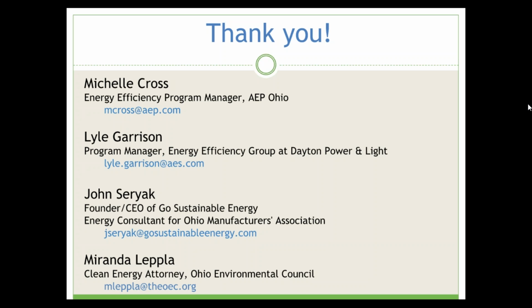Yeah, this is John. I think the answer is yes, it can be, and it's a cost-benefit thing. If you're going to be providing ancillary services or putting electricity onto the grid, it's not necessarily the same dollar per kilowatt hour rate that you get when you're saving versus when you consume. So you have to pencil it out. I think most projects intentionally cap their system size around what the facility can displace on site, but that's not to say someone might find a model where they can monetize the ancillary services. You just have to put the numbers there.